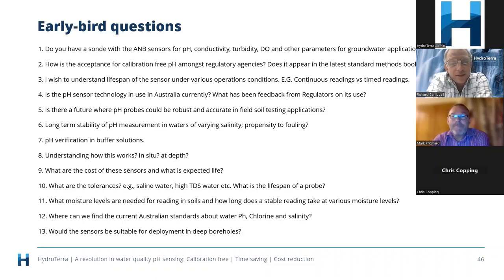That's a good question, and a very common one. We're looking to see how we can provide an answer for this, because people take it, put it in a buffer solution to make sure that it's operational. We don't operate today in buffer solutions, so we need to say to people, trust us—but we do need to provide a way of proving the operation to a pH level. That's something we're working on, because it's a very common question. We've got units out—I've mentioned with the Dutch at the moment, and also in North America and other areas—where they've taken the unit, stuck it in a buffer solution, and can't understand why it's not reading correctly. Because of the technology, we don't work in that way, but we're looking at providing a solution so people can verify operation.